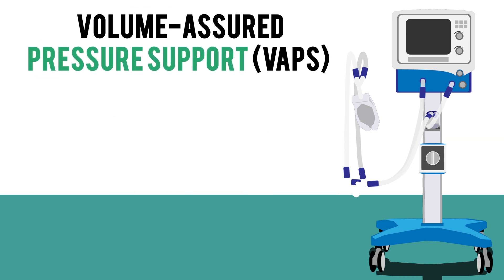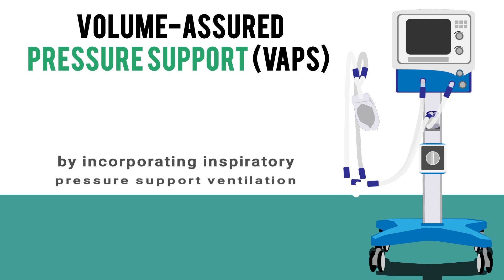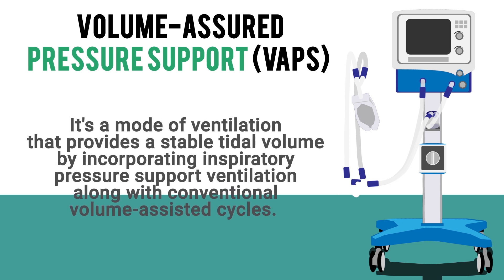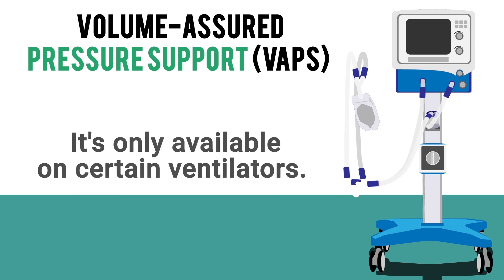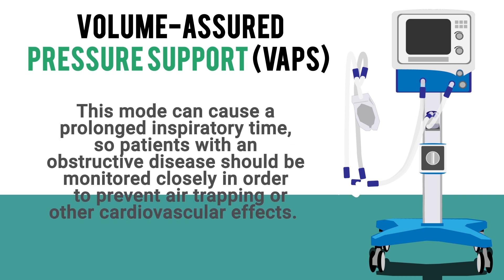VAPS, or Volume Assured Pressure Support, is a mode of ventilation that provides a stable tidal volume by incorporating inspiratory pressure support ventilation along with conventional volume-assisted cycles. This mode is only available on certain ventilators. One important consideration: VAPS causes prolonged inspiratory time, so patients with obstructive disease should be monitored closely to prevent air trapping or cardiovascular effects.